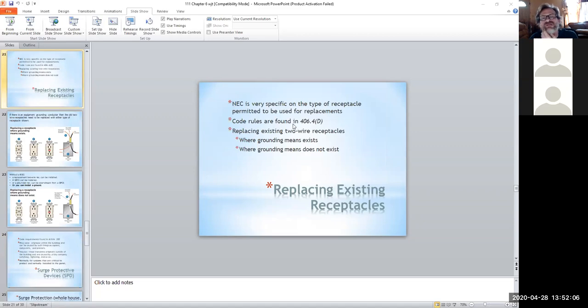They do have codes on this, right? If we looked up in 406, section 4, they have requirements for replacements and things like that. So let's say you're doing older style homes where you didn't have a ground - you can't buy those type of receptacles now, since they all have that ground connection. Instead of doing a very costly wire repull, especially with sheath style wiring like Romex, because if it's the old 2-wire style, you'd literally have to repull the whole thing to get 3-wire in there with the ground.